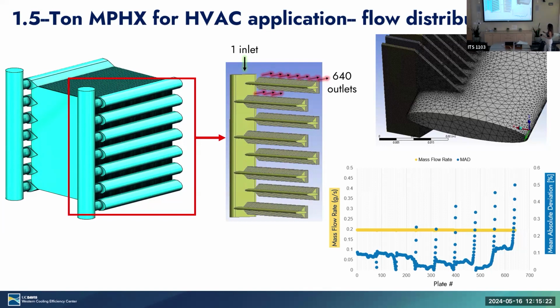Well, so after we ran the simulation, the yellow line here is showing us the mass flow rate that is expected in every single outlet of these plates. And as you can see, the line is pretty horizontal, so we are hoping to expect an even flow distribution. Here in the right side, I'm showing the mean absolute deviation, and the highest we had was 0.5%, which is pretty good. So we can say that the flow is actually distributed evenly across the heat exchanger. And we ran the simulations for a total flow rate of 2 gallons per minute, as well as 5 gallons per minute.